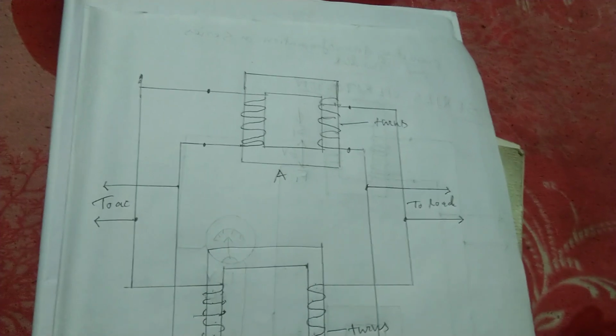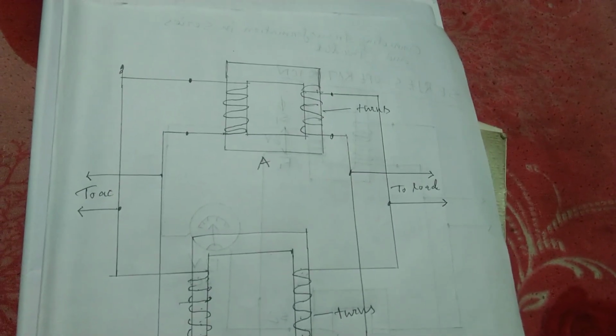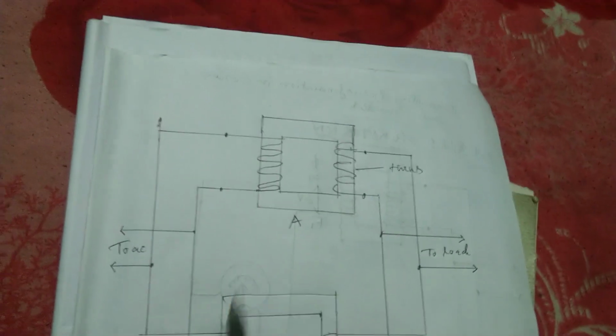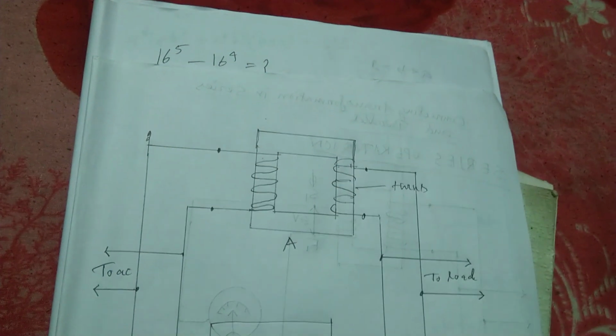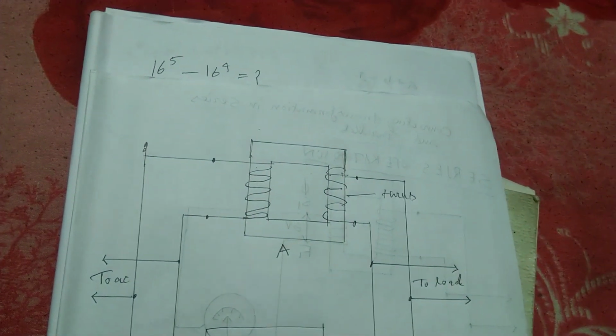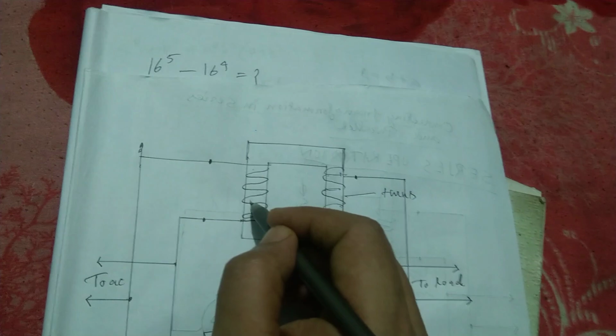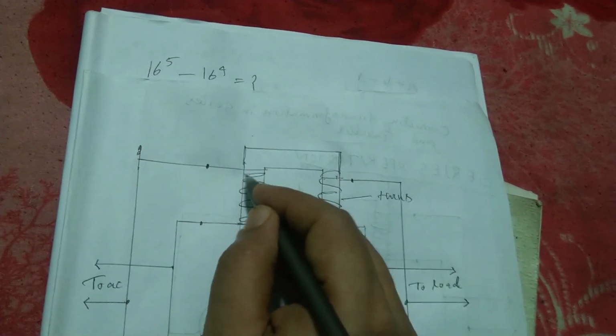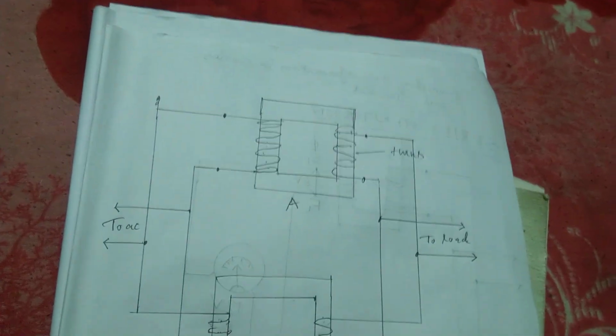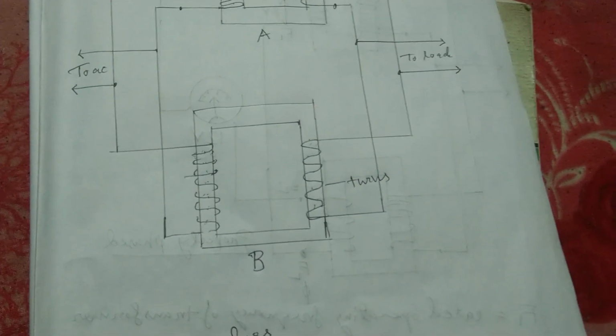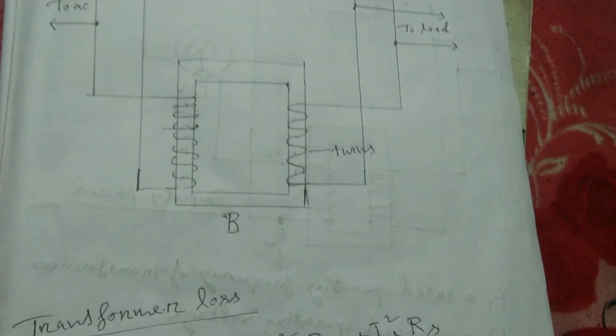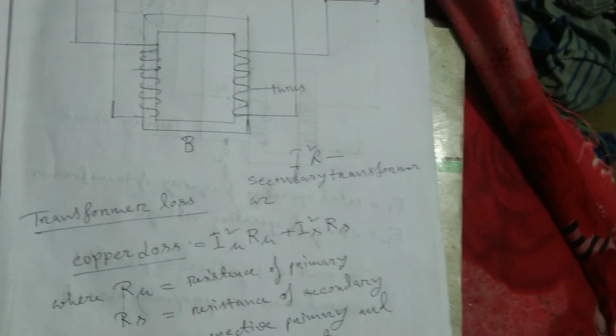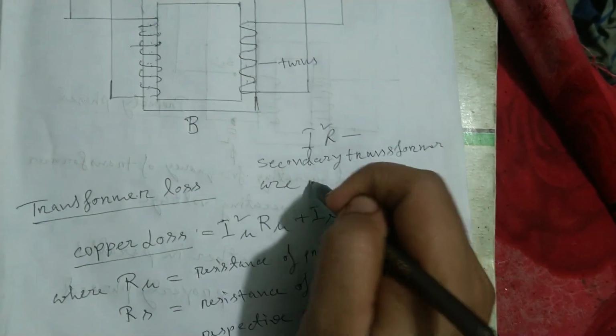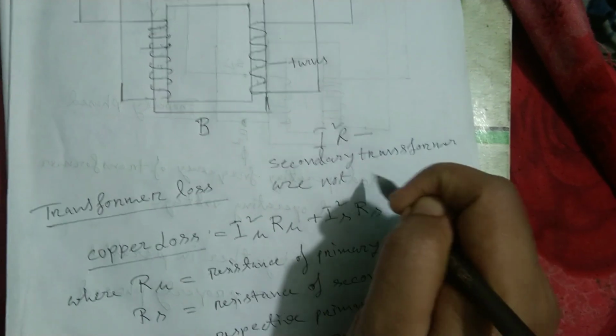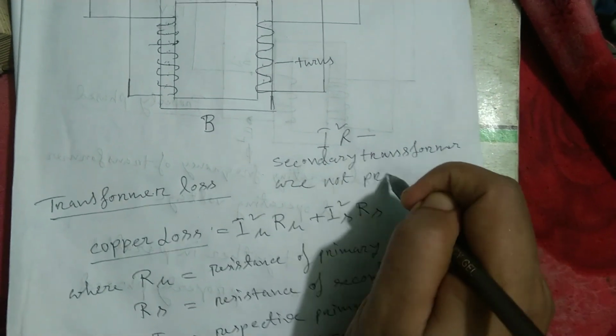And now another factor, the same number of primary and secondary turns. Primary turns also the same, secondary turns also the same. 1 2 3 4 5 6 7. So the same number of turns.